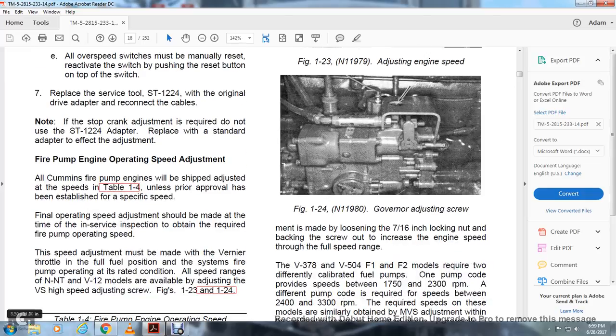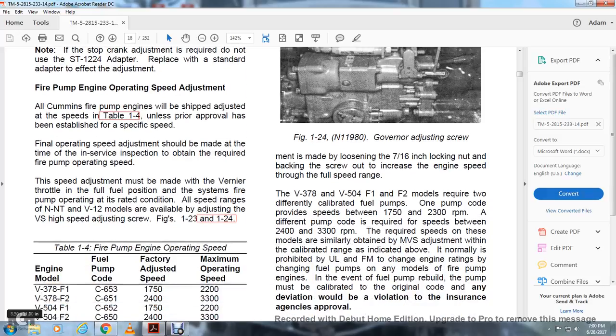Fire pump engine operating speed adjustment. All Cummins fire pump engines will be shipped and adjusted with the speeds of Table 1.4 unless prior approval has been established for a specific speed. Final operating speed adjustment should be made at the time of the site inspection to obtain the required fire pump operating speed. Speed adjustment must be made with the throttle in the full fuel position. The NT and V12 models are available with the VS high-speed adjusting screw, figures 123 and 124.